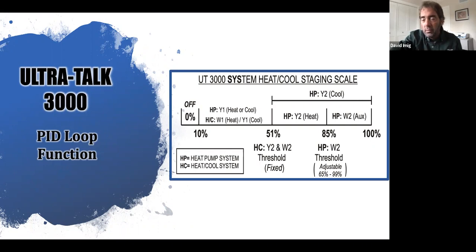Once I see my target temp of 142, I stop my percentage at that particular point. If that's at 48, I stop at 48, I stay at 48. If I happen to go slightly above that 142, I will stage back down in 2% increments. I go up in 1% increments, I go down in 2% increments, and settle in where I'm achieving and maintaining that 142 degrees.